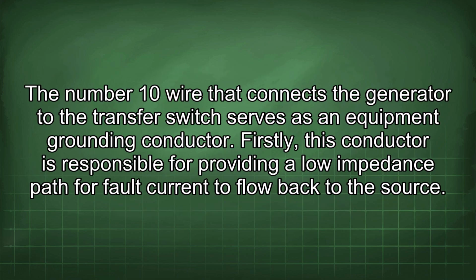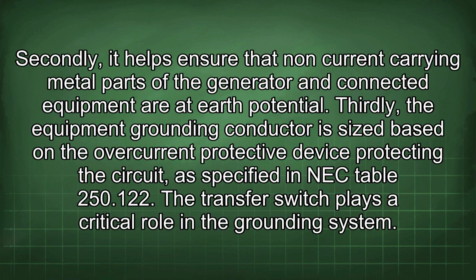The number 10 wire that connects the generator to the transfer switch serves as an equipment grounding conductor. Firstly, this conductor is responsible for providing a low impedance path for fault current to flow back to the source. Secondly, it helps ensure that non-current carrying metal parts of the generator and connected equipment are at earth potential. Thirdly, the equipment grounding conductor is sized based on the overcurrent protective device protecting the circuit, as specified in NEC Table 250.122. The transfer switch plays a critical role in the grounding system.